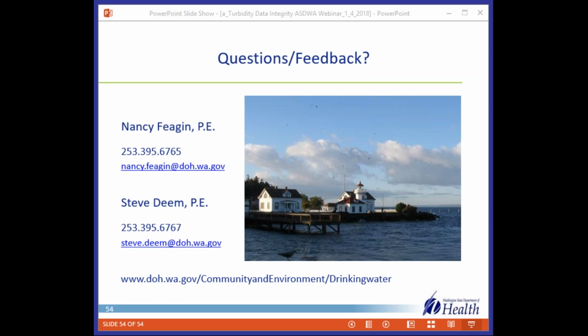And one of the systems that we went to had multiple filters, and their turbidimeters were not all within the specified range. They had a Hach service contract, so they don't always cover everything, such as sample flow rate. So this comes back to our big push on SOPs. And in your SOPs is still, here's what should be done to each instrument. Here's how we maintain it. Who does it? That's kind of up to each utility, whether you do it contracted out or you have your own staff.